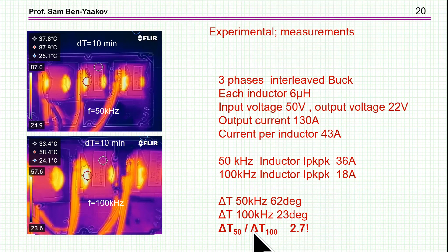So the ratio of the temperature rise is about 2.7. That's a lot. So this shows that the increase in the delta B, the B_max, as you go down the frequency is very important, very harmful.